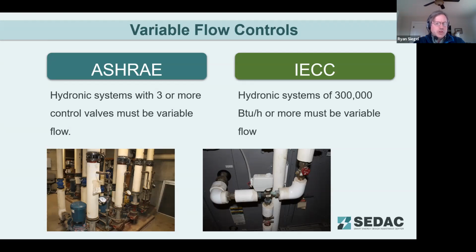And as Sean mentioned earlier, good practice, because we see many of these HVAC systems, what has changed over the last 15 or 20 years of a building. You might consider doing a load calc, even if it's not necessarily required, because you might be able to downsize the unit, which may save you some equipment and labor costs to do that install and make that upgrade, plus better comfort, better control, and potentially lower utility bills.